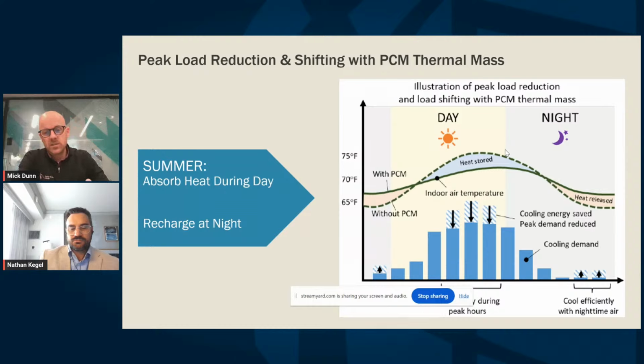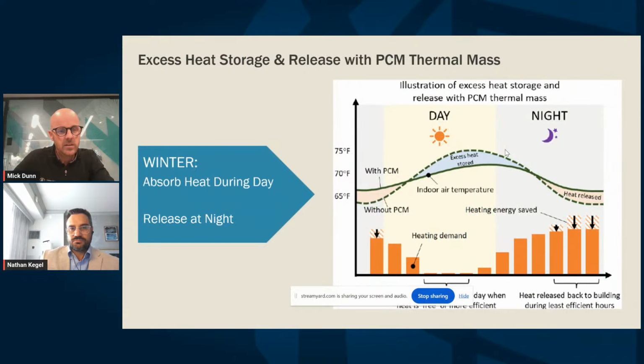The result is that in the afternoon hours, if we can shrink the temperature and push the peak further into the afternoon, we're generally saving energy at the peak of the afternoon, hopefully when peak demand and energy consumption costs are greatest. Overnight, we're releasing that, hopefully with fan energy, sometimes with more efficient cooling, and recharging for the next day. That may simply mean having a set point of say 70 to 72 degrees early in the morning, favoring economizer cooling, then setting it up so we can absorb that later in the day. We'll see that in some of the case study information I'll share later.